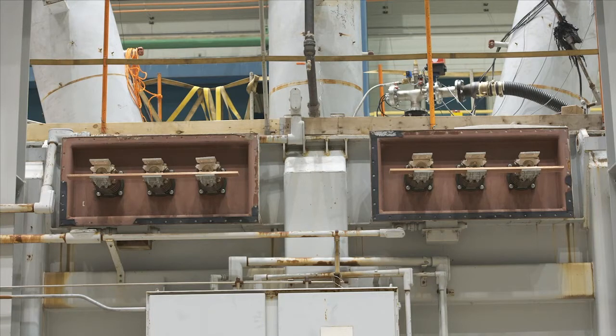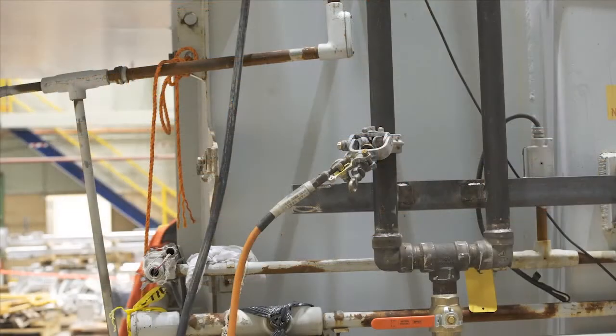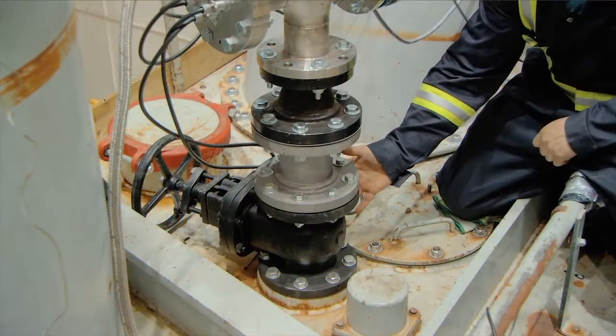For high currents greater than 100 amperes, bolts instead of clamps should be used. Make sure that the bolts are properly tightened. Also, when drying an auto transformer, the LV side has to be short-circuited. If the transformer has a tertiary winding, this one is normally left open or not connected. Connect the grounding cable to the transformer tank. Connect the vacuum flange with the vacuum regulation valve to the transformer.